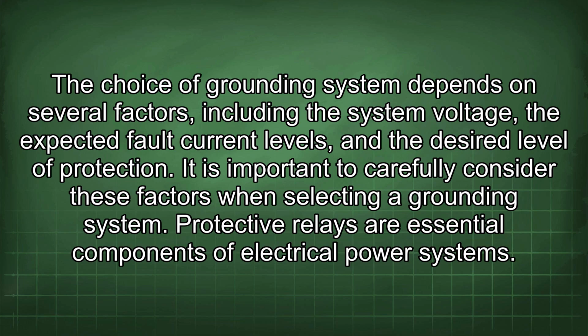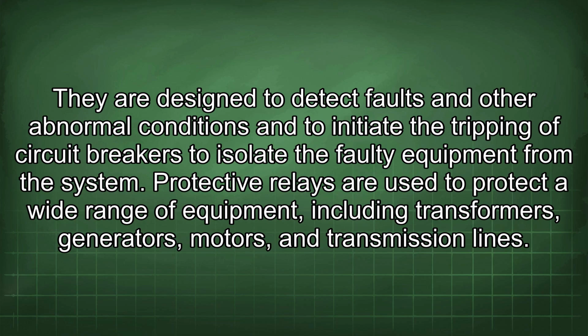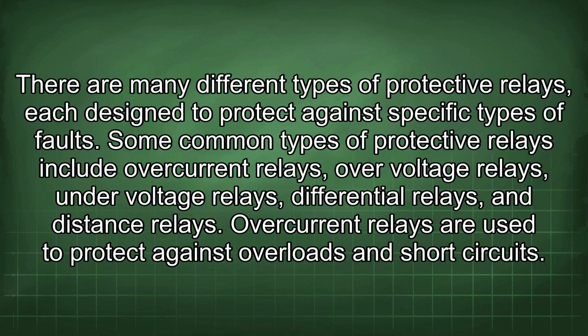Protective relays are essential components of electrical power systems. They are designed to detect faults and other abnormal conditions and to initiate the tripping of circuit breakers to isolate the faulty equipment from the system. Protective relays are used to protect a wide range of equipment, including transformers, generators, motors, and transmission lines. There are many different types of protective relays, each designed to protect against specific types of faults. Some common types of protective relays include overcurrent relays, overvoltage relays, undervoltage relays, differential relays, and distance relays. Overcurrent relays are used to protect against overloads and short circuits.